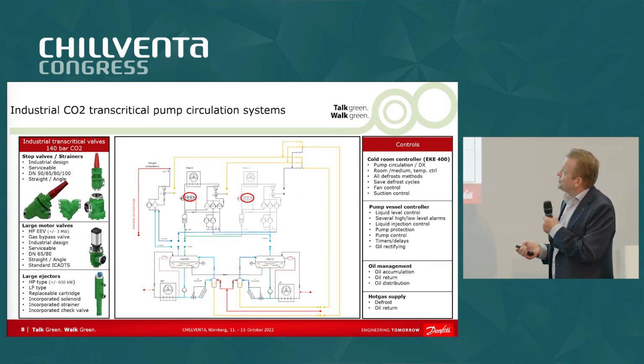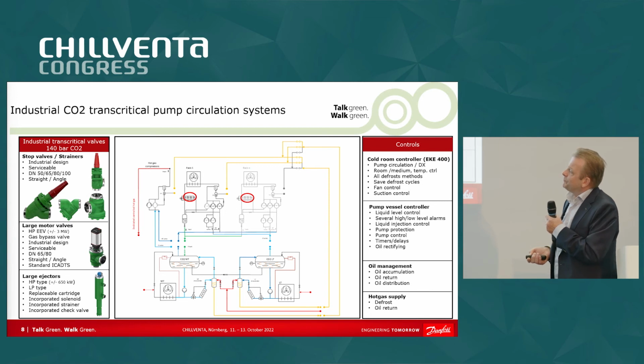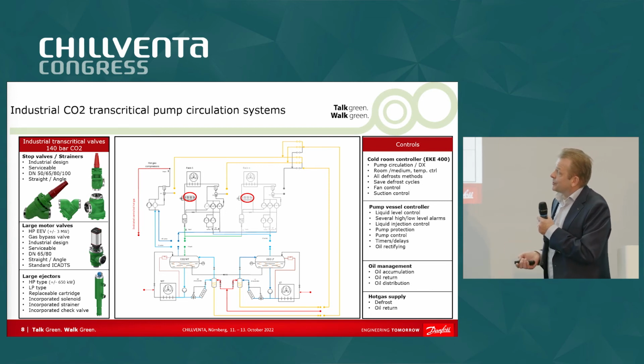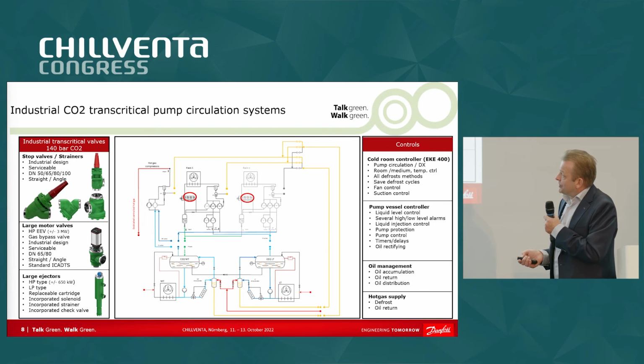But also here we need much bigger ejectors than available on the market. So we have it on the booth. You can look at it. It's a 600 kilowatt ejector, and the idea is that you mount a few in parallel to get the total capacity. So we have high pressure ejectors, high pressure lift ejectors, and low pressure lift ejectors. It depends on the situation what you want to do.